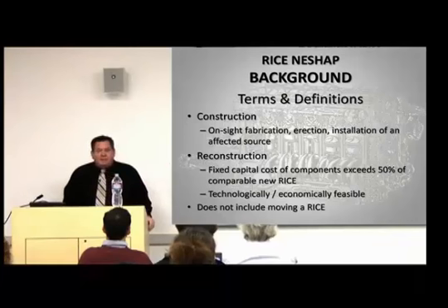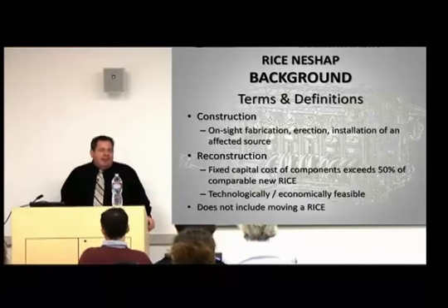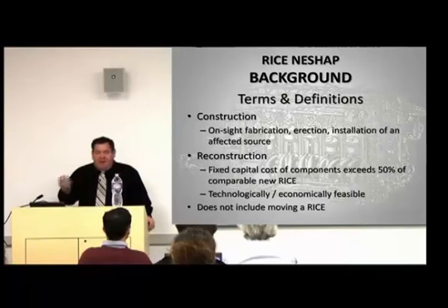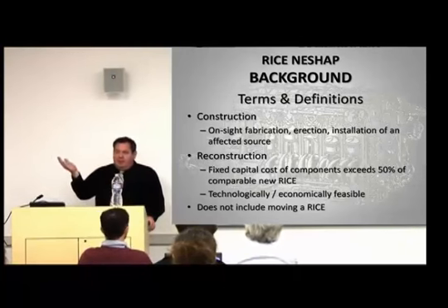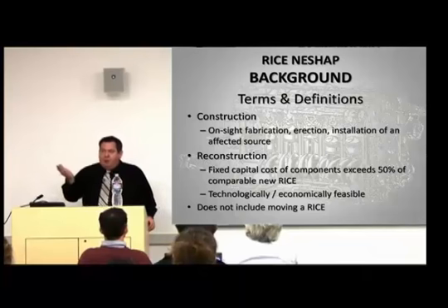But in many cases, especially with these big behemoth engines, I see some old Ingersoll Rand and Dresser engines that are back from the 50s. Nobody's making updated rebuild kits for these. So oftentimes it's not going to be economically or technologically feasible for reconstruction. But the definition is the capital cost of components exceeds 50% of the cost of a comparable new engine.